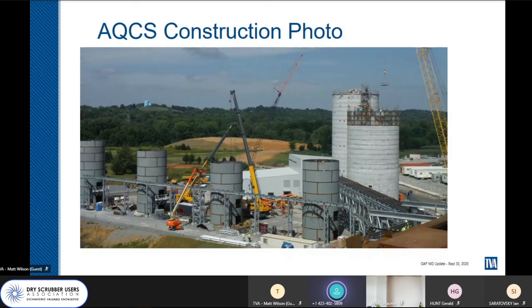During the construction of the pebble lime storage silos, these main storage silos, we did leave space for crushers. So our reagent specification now is pebble lime. It's sized 1/8 of an inch by 0 top size, but leaving space for crushers allows us to competitively bid pebble lime on the open market. Of course, we would need to go in with crushers, and then we could crush them on site. There are suppliers locally that can supply 1/8 of an inch by 0, so at present we don't have to run the crushers.